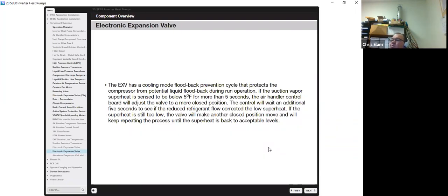The EXV has a cooling mode floodback prevention cycle that protects the compressor from potential liquid floodback during run operation. If the suction vapor superheat is sensed to be below 5 degrees for more than 5 seconds, the air handler control will adjust the valve to a more closed position. The control will wait an additional 5 seconds to see if the reduced refrigerant has corrected the low superheat. If the superheat is still low, it will make another closed position move. Keep repeating the process until the superheat is back to acceptable levels.